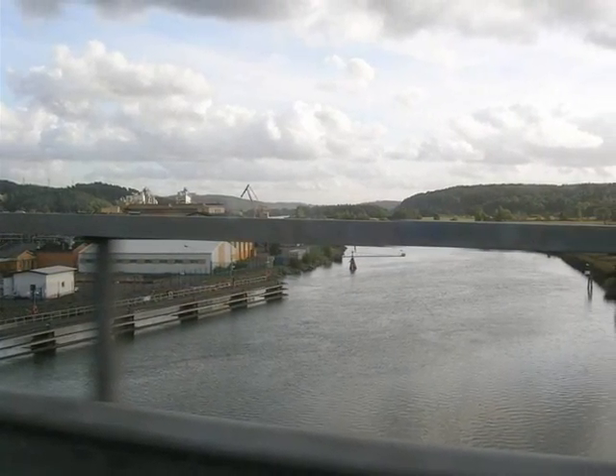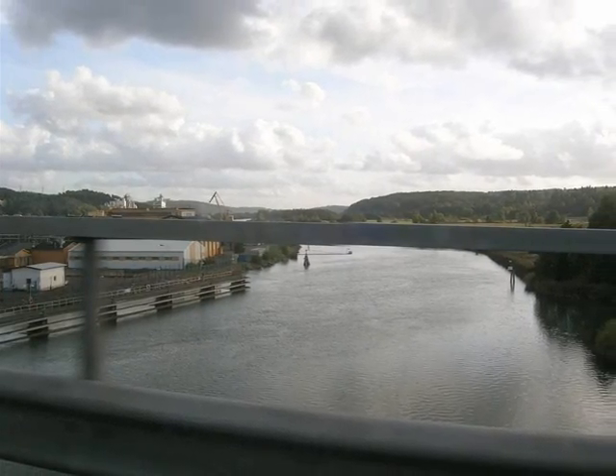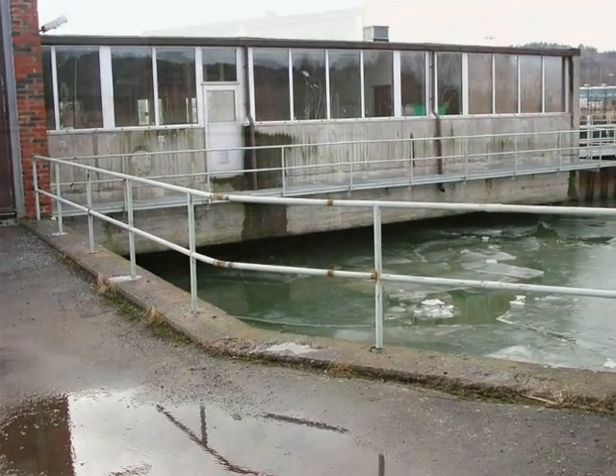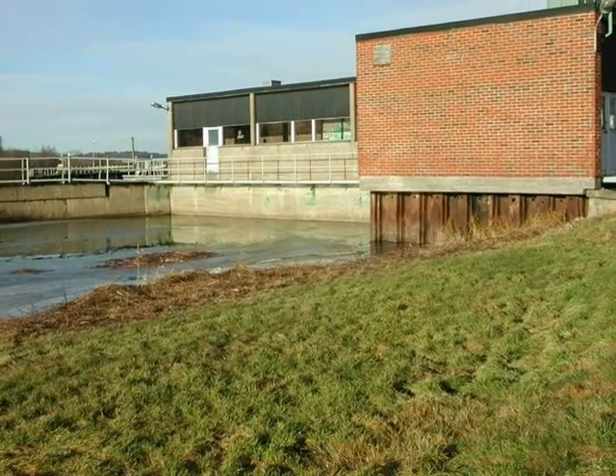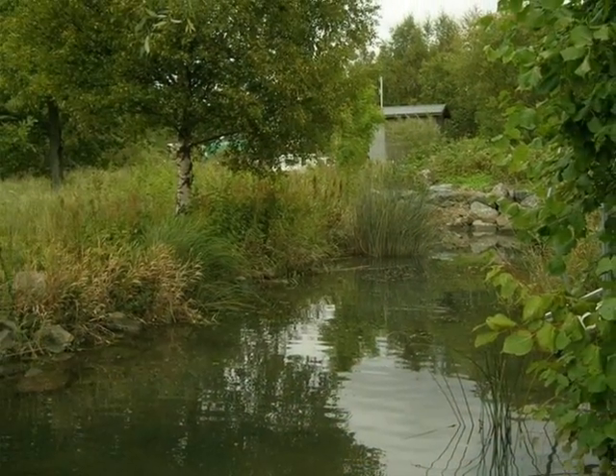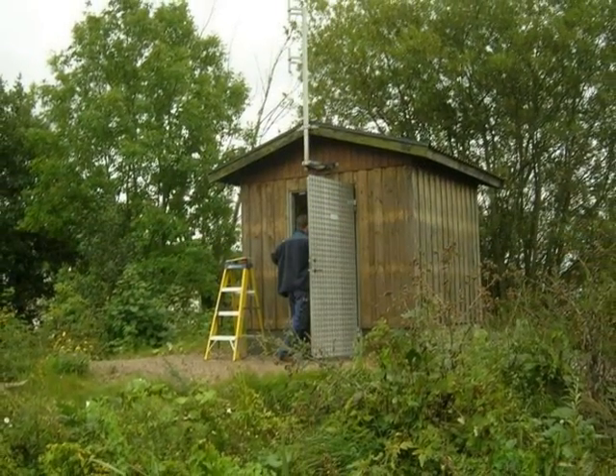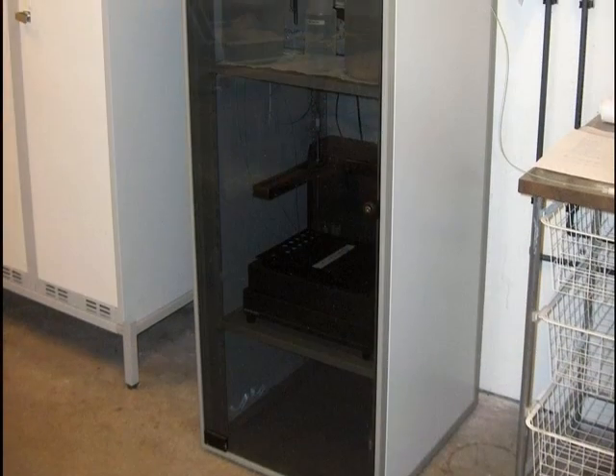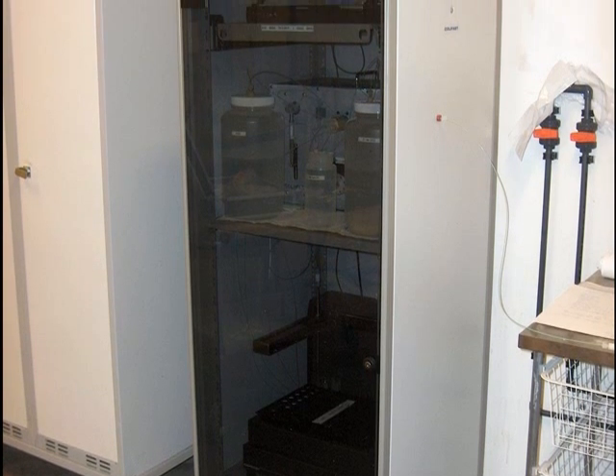In the city of Gothenburg in Sweden, the drinking water is mainly from the river Götaälv. A CALM at the intake monitors E. coli by a five-vial MPN method two times a day, and the same method is used at a second CALM upstream. The results of the CALM are one of the parameters that determine whether the intake should be closed and a reservoir used instead, or whether the treatment of the water should be increased.